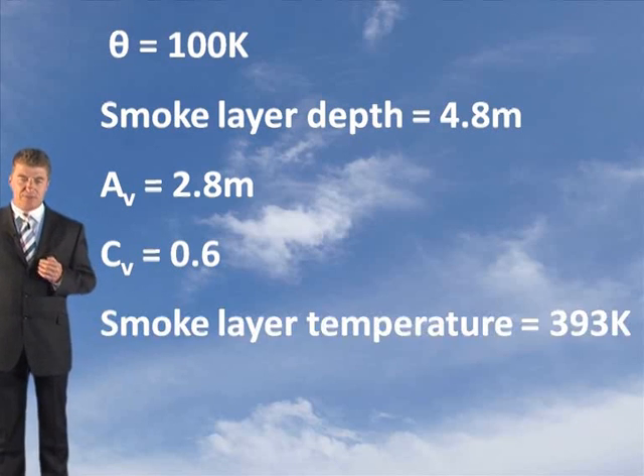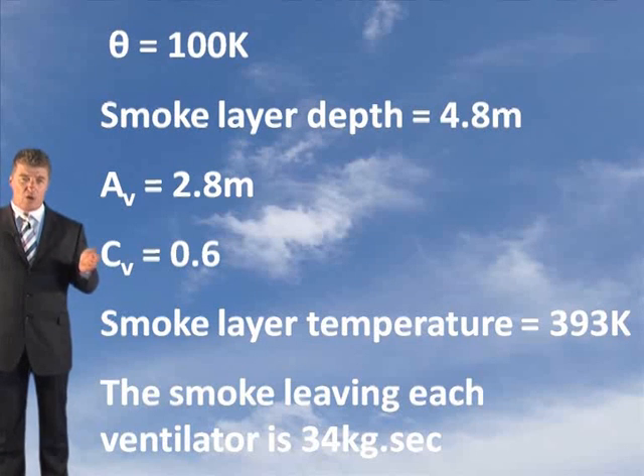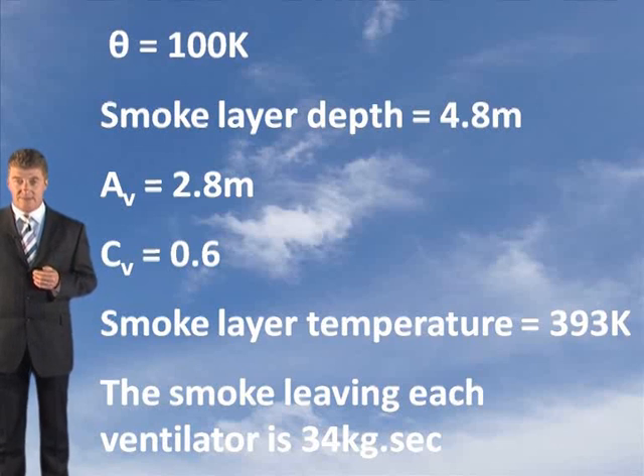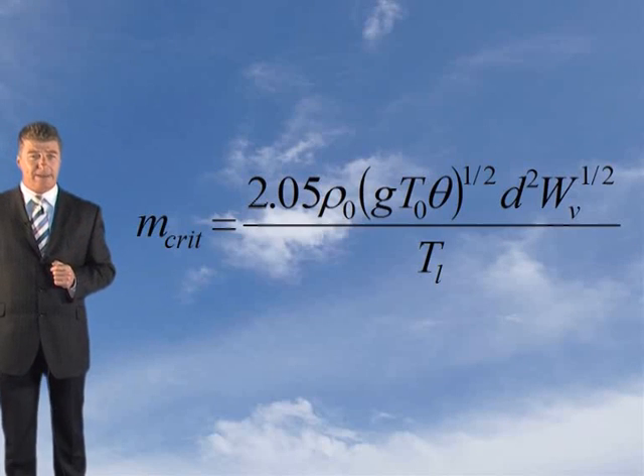Your temperature of your smoke layer is 393 degrees Kelvin and the smoke leaving each ventilator has been worked out at 34 kilograms per second. Now as the ventilator is located more than 2 metres away from the edge of the reservoir, this is the formula you should be applying.